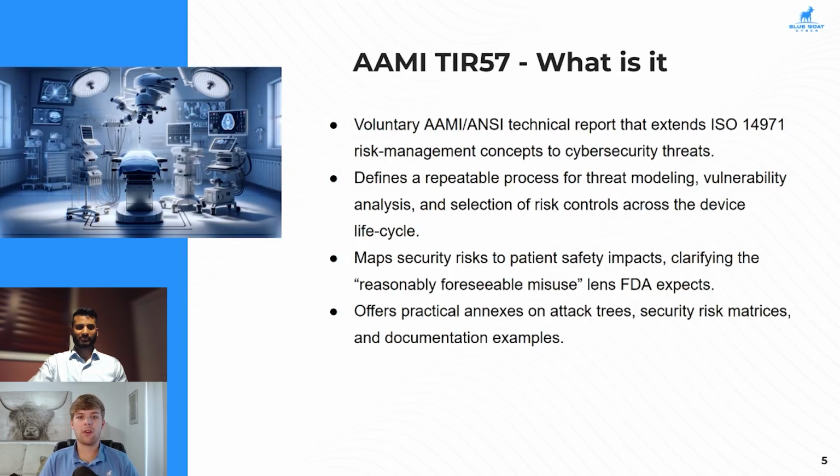We're also mapping security risks to patient safety impacts, clarifying the reasonably foreseeable misuse that the FDA lens expects to see. Everything should be risk-based when we're going through the FDA submission, as opposed to saying there's a one-size-fits-all solution. This also talks about some practical vectors for attack trees, security risk matrices, and documentation examples so that we have something to start working off of when we're going through this process.